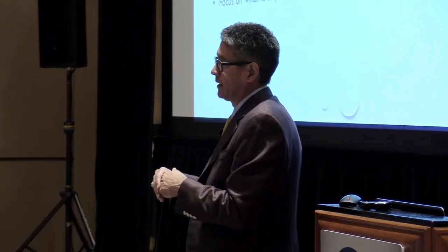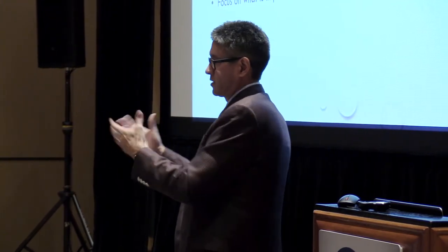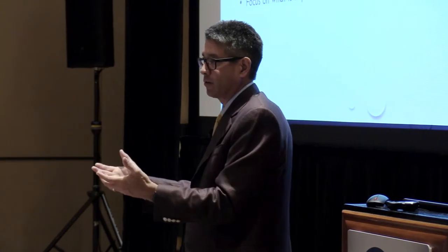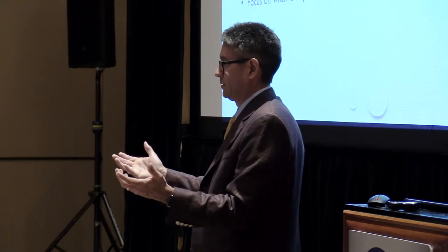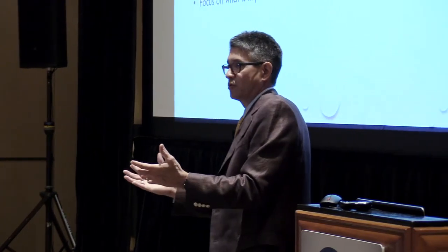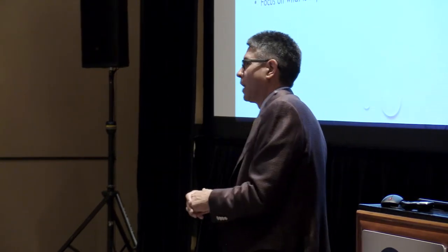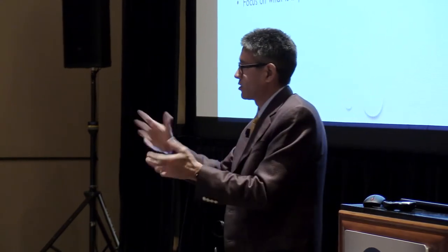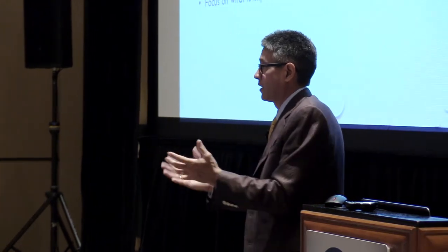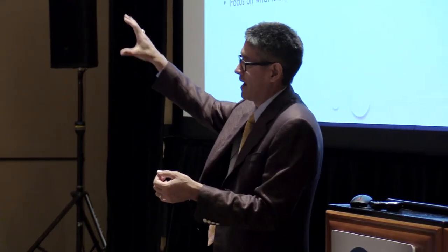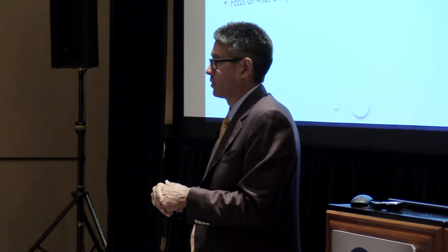The one thing I'll say, don't get hung up too much in trying to get all this built into a system. How many people have had callbacks on reheat systems because they're not working, they're not heating? They're very forgiving. So if you're going to take the owner's money and start spending it on trying to measure flow to every reheat coil, I don't know if that's a wise decision for the owner. Do you really need that? Certain situations you might, but don't let that engineer start driving down that path of all this technology to take a simple system and make it more complex when it doesn't need to be.